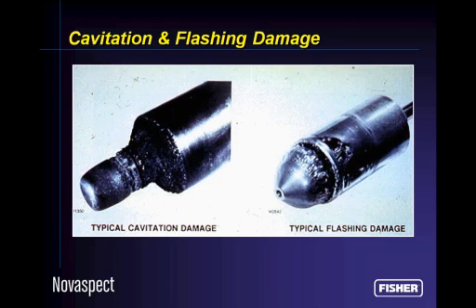Well, erosion and corrosion are pretty nasty, and they make quick work of control valves. Let's discuss a couple other flow anomalies that really create problems for us and have us replace valves more often than you, the customer, would think we need to, and more often than we would like to ourselves. So we have flashing and cavitation phenomena, and the cause is similar for both, but there's a little difference in the process that creates flashing and cavitation.